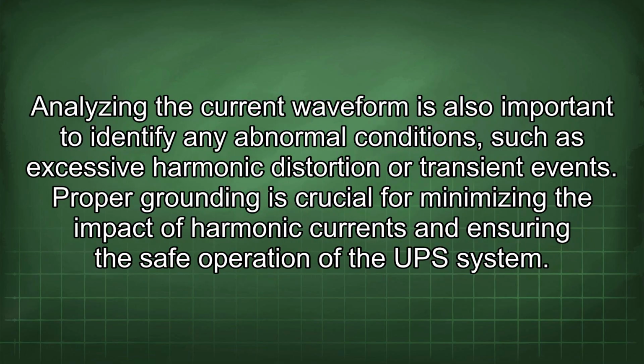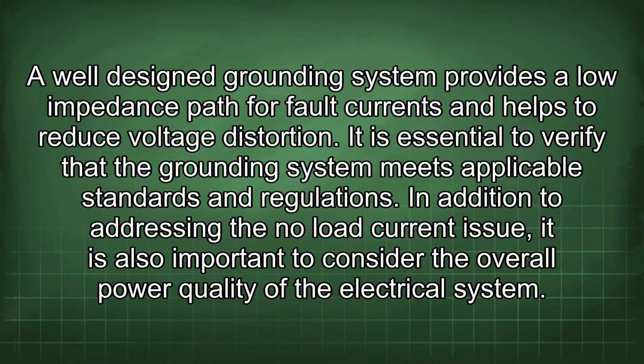Analyzing the current waveform is also important to identify any abnormal conditions, such as excessive harmonic distortion or transient events. Proper grounding is crucial for minimizing the impact of harmonic currents and ensuring the safe operation of the UPS system. A well-designed grounding system provides a low-impedance path for fault currents and helps to reduce voltage distortion. It is essential to verify that the grounding system meets applicable standards and regulations.